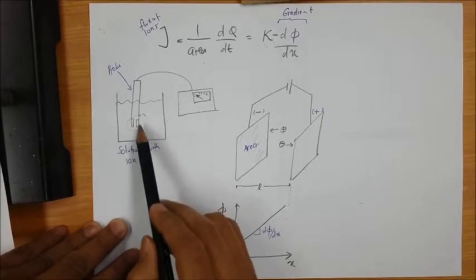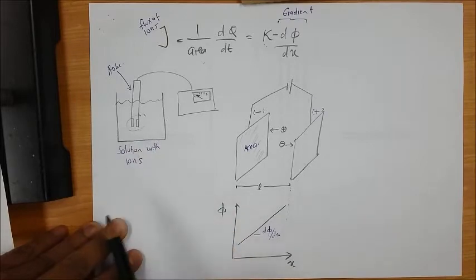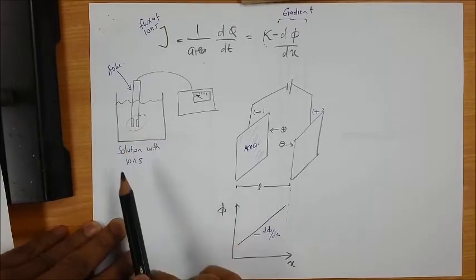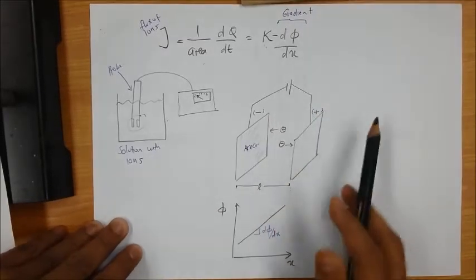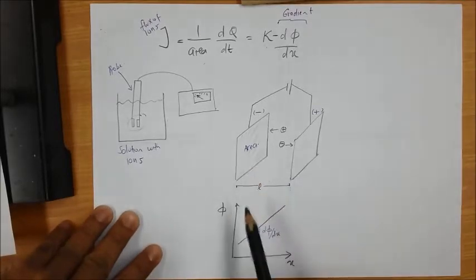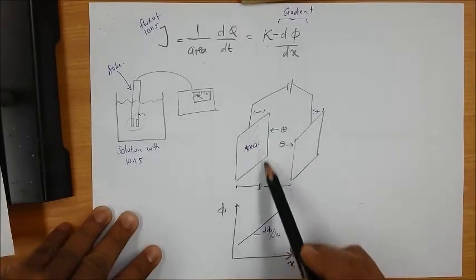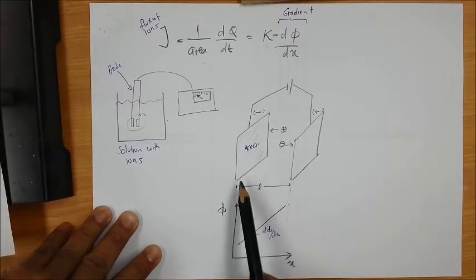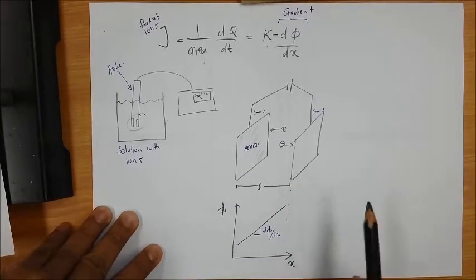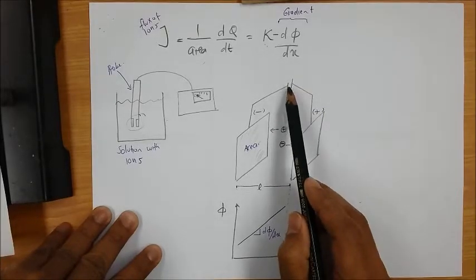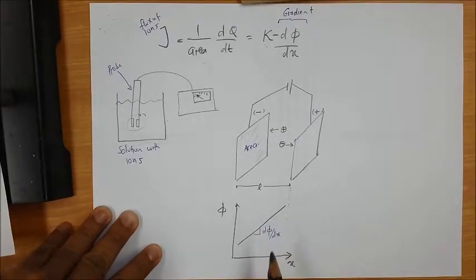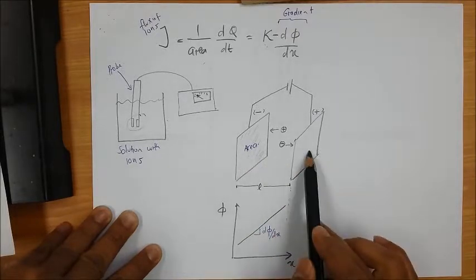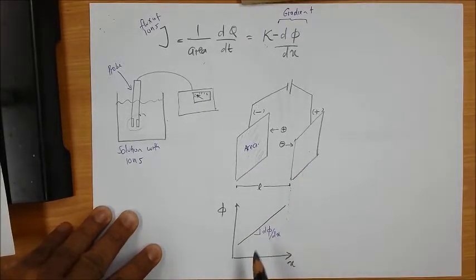At the tip of this conductivity probe, it looks something like this. It is composed of two electrodes, negative and positive, with a specific area and a specific separation distance. Once a potential is applied, there will be an electric potential difference between the negative electrode and the positive electrode, right?